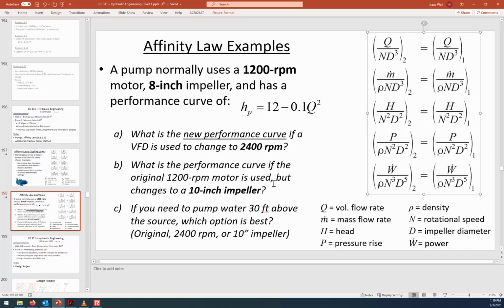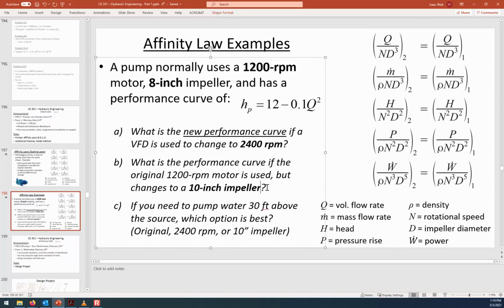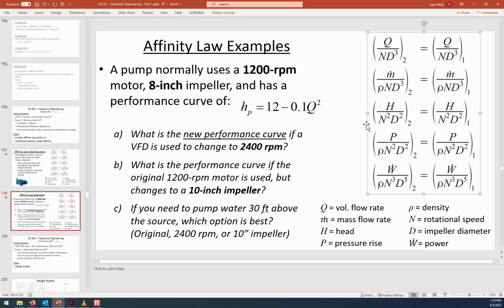What is the performance curve if the original 1200 RPM motor is used, but now you switch to a 10-inch impeller? So D is going to be changing. You're going to be changing D, and so D is a term in both the first and the third, but the rotational rate N is going to be 1200 for both of them.